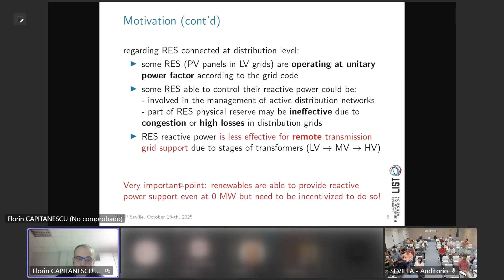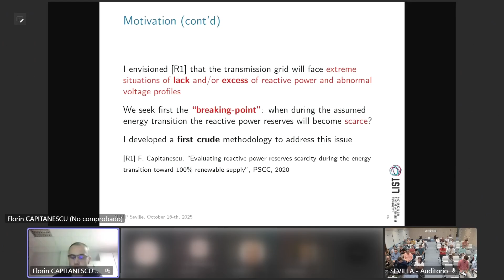Based on all these thoughts on reactive power issues, I published a paper in 2020 at the Power System Computation Conference, arguing that under these conditions the transmission grid will face situations of lack or excess of reactive power. For that reason, we need to identify when this situation could occur, what I called the breaking point, the point during the energy transition, given a certain penetration of renewables, when reactive power will become scarce. I developed a first crude methodology, a proof of concept, for this issue in that work.